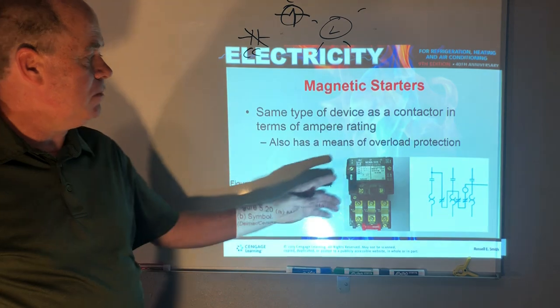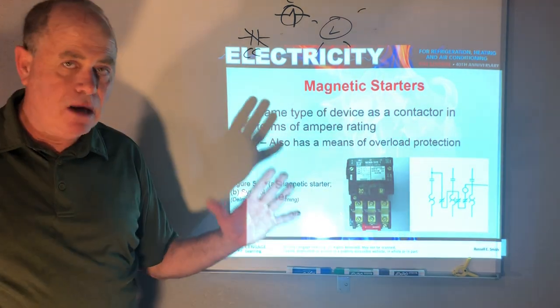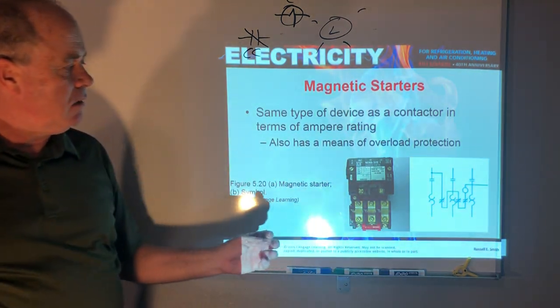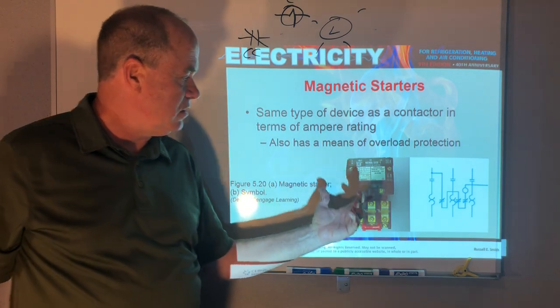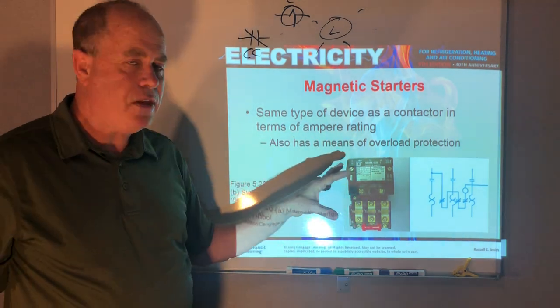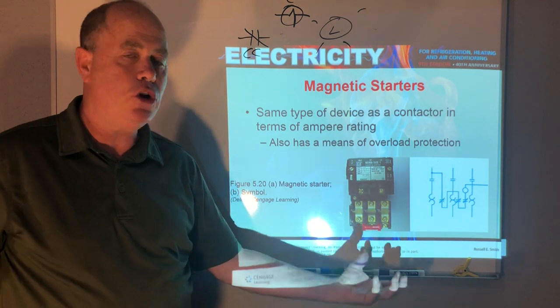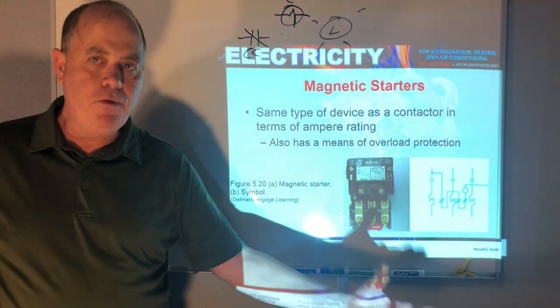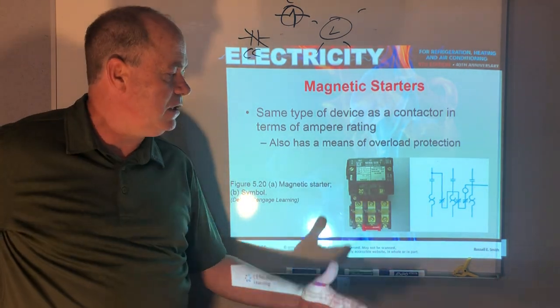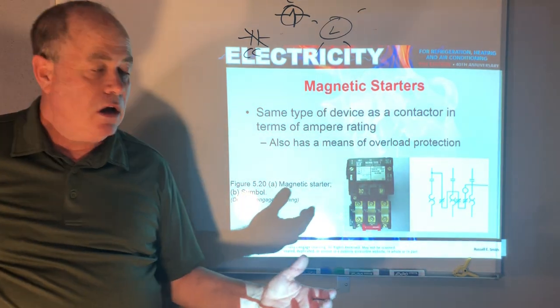Now this is a mag starter, a motor starter, also sometimes referred to more in electrical work as a line starter. And it's nothing more than a contactor that has built in overload protection for the load that it serves, like a very large fan or compressor.